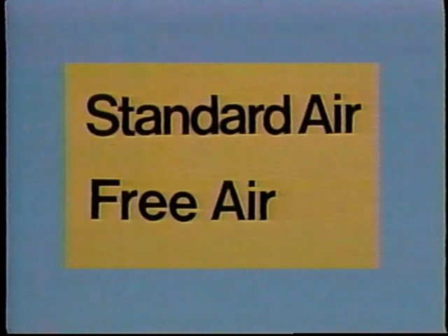So when referring to flow rates or compressor capacities, we must use what is known as standard air. Right here I should explain the difference between standard air and free air. Free air is a common term and means air available to the intake of a compressor. Since the condition of free air varies from day to day and location to location, we need a way of describing air that is consistent and never changes. This we call standard air.